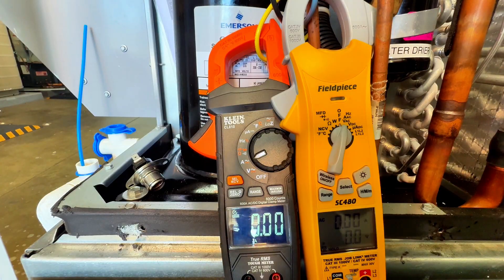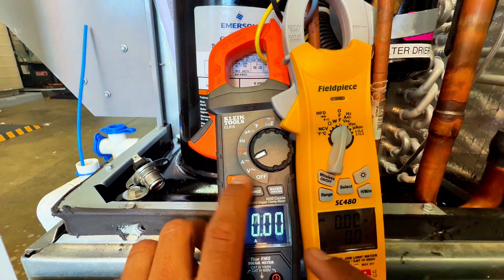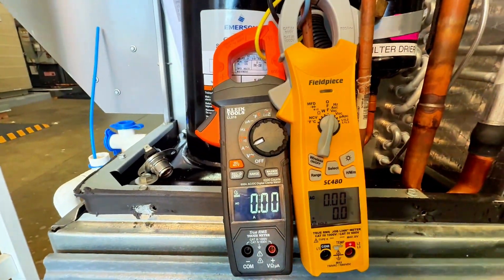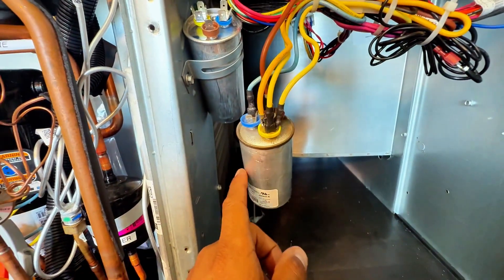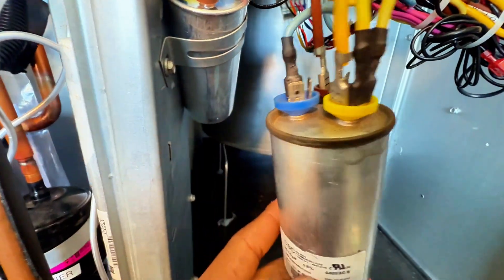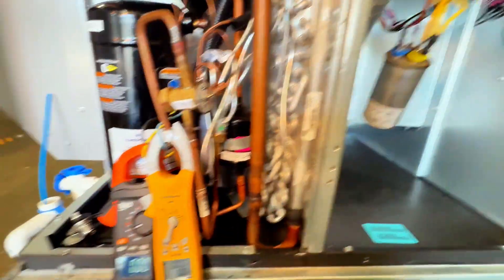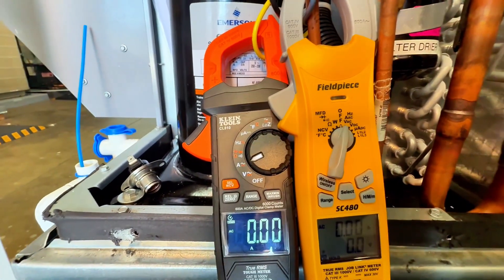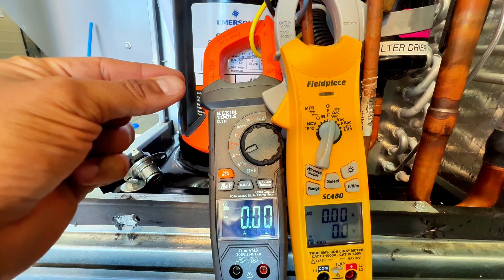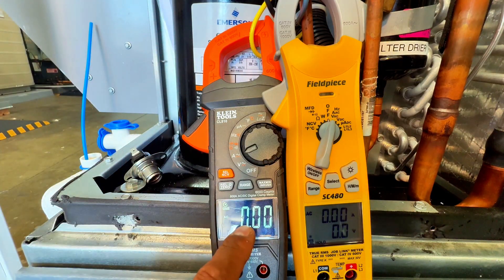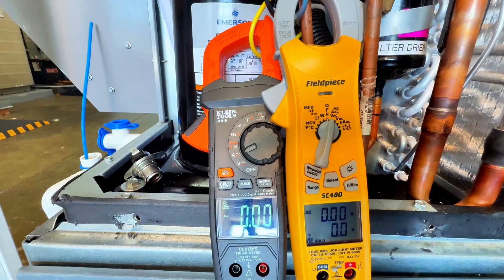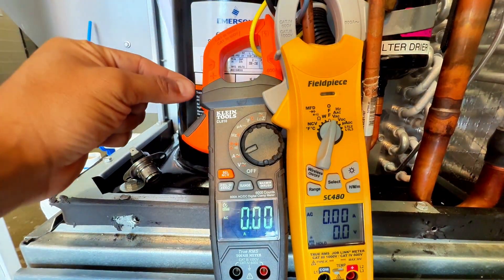Okay, so let me go ahead and show you guys so you guys can see the numbers as I turn on. And yes, that glare is the worst thing that can happen to someone recording. Okay, there we go. So as I said, run and start. Okay, run winding and start winding. So look at those numbers right now. I'm going to go ahead and call for it. Okay, so that's my run winding and that's my start winding. Both windings are pulling current right now. But this is how it would look if the capacitor is healthy and it's working. It wouldn't be pulling a lot of amperage. But I'm going to go ahead and get these numbers and write them on the whiteboard. And then now we're going to be checking the amps on the start and run winding with a bad capacitor now.